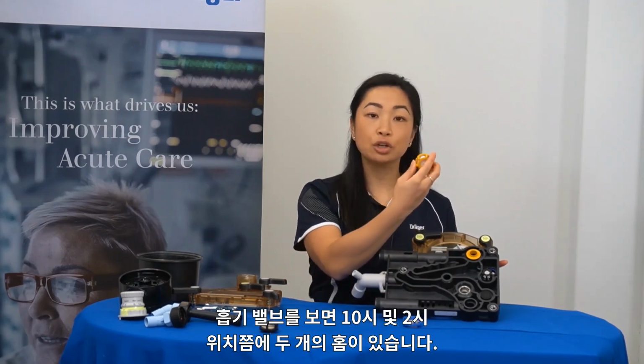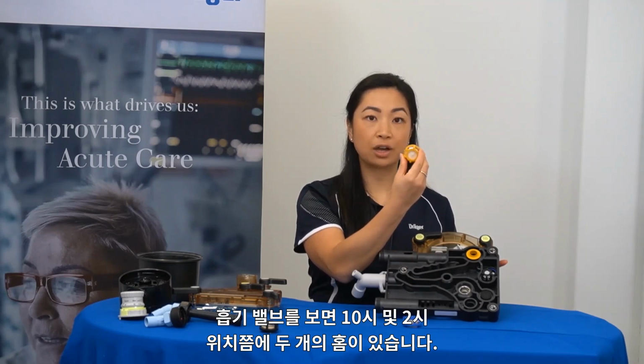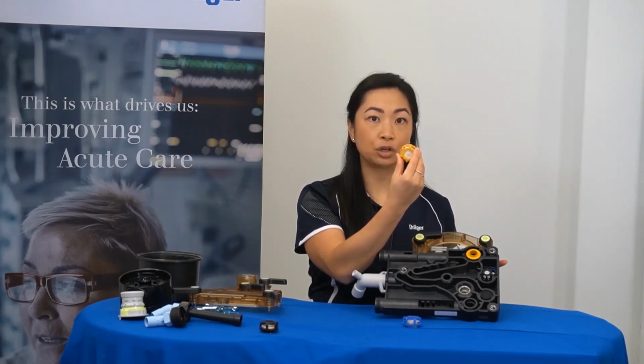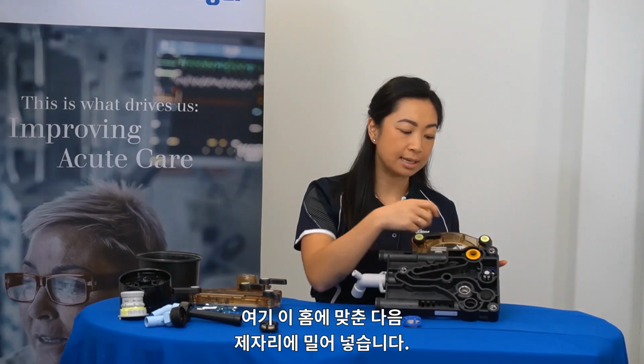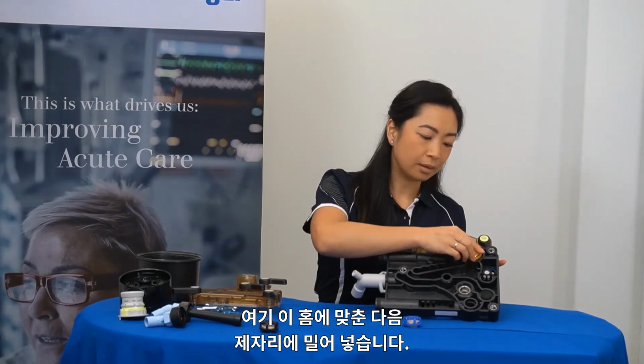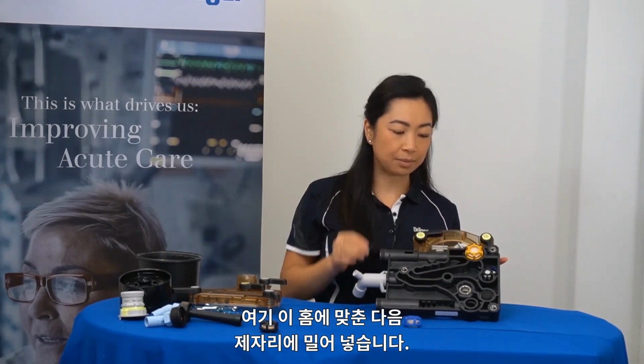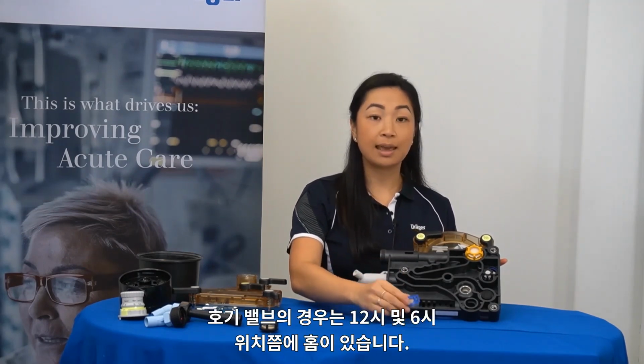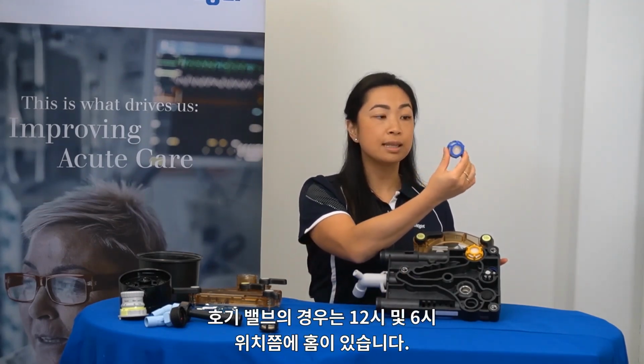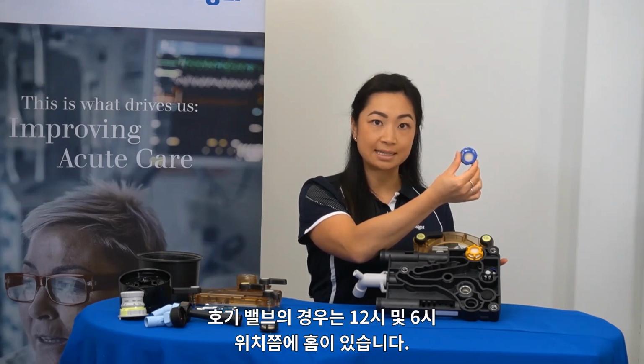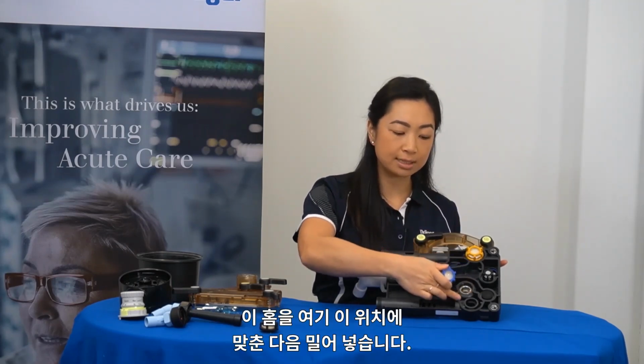You'll find 2 notches on the inspiratory valve at roughly 10 and 2. This should align with the notches seen here. And then pushing it into place. With the expiratory valve, you'll notice that the notches are at 12 and 6. This will align with the notches in this position here.